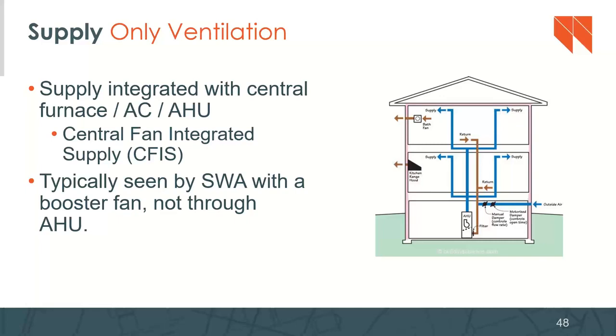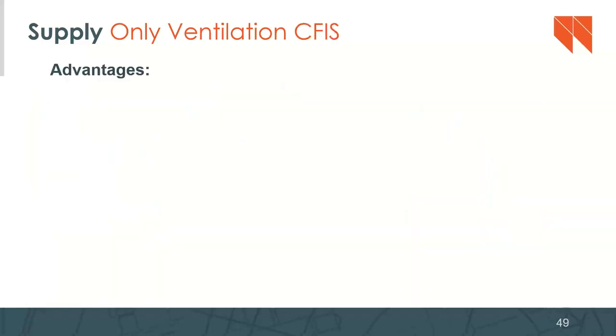So the advantages there is that we now can have a more reliable flow rate, and we know that we're going to at least meet the minimum. And if it's got any speed control or dampers on it, we can make adjustments to it and get it to the flow rate that we need based on the size of the building and the number of people living there. All that stuff is also governed by ASHRAE. So booster fan, what are some of the advantages of this?